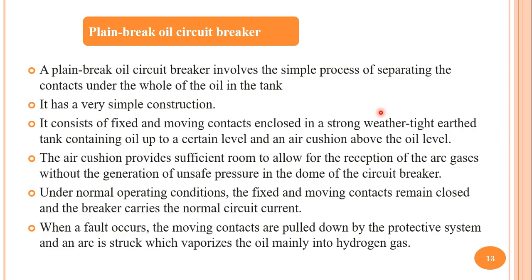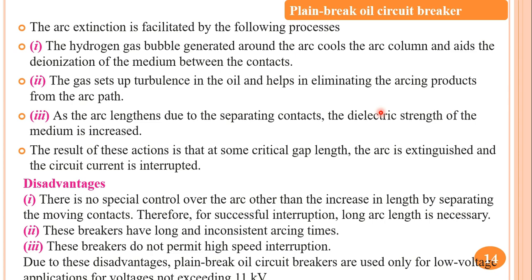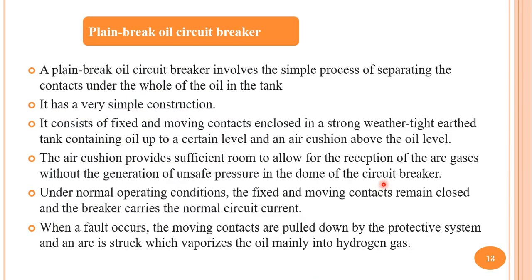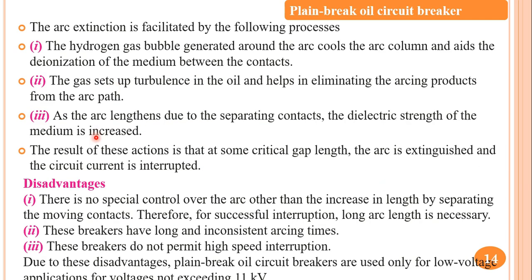In the plain break oil circuit breaker, arc extinction is mainly done by increasing the length of the arc — as the moving contact is moved from the fixed contact, the length of the arc increases. An air cushion is provided for accommodating the hydrogen gas. These breakers have long and inconsistent arcing time depending on the current and the length of the arc, so arcing time is inconsistent.